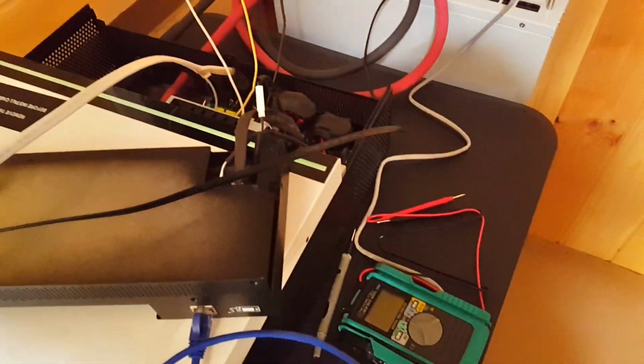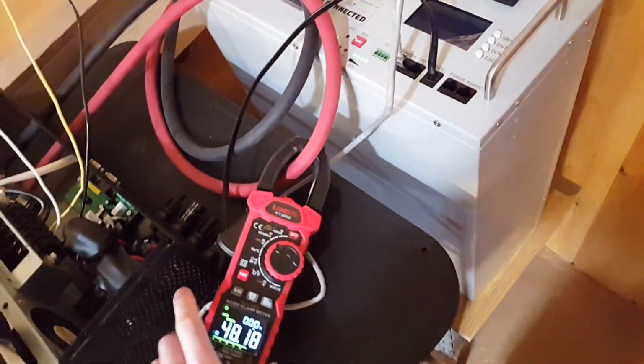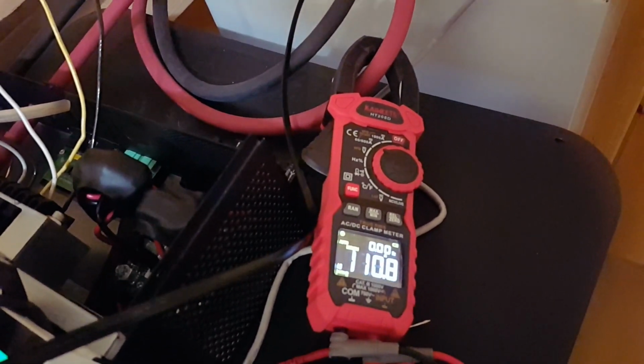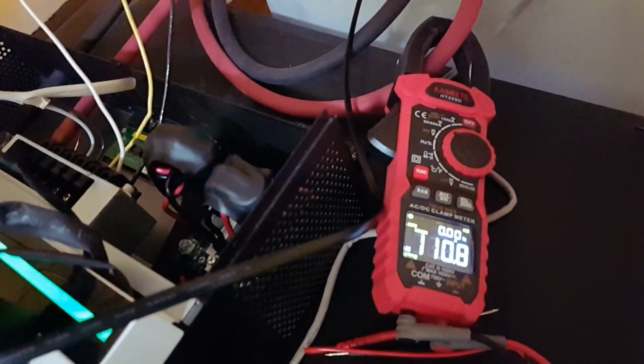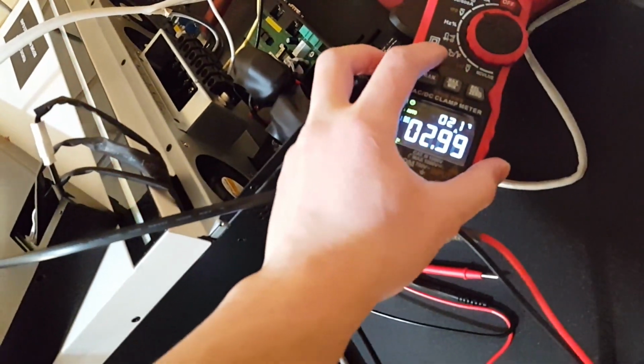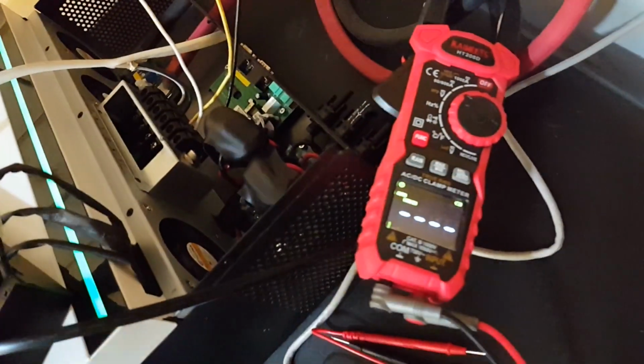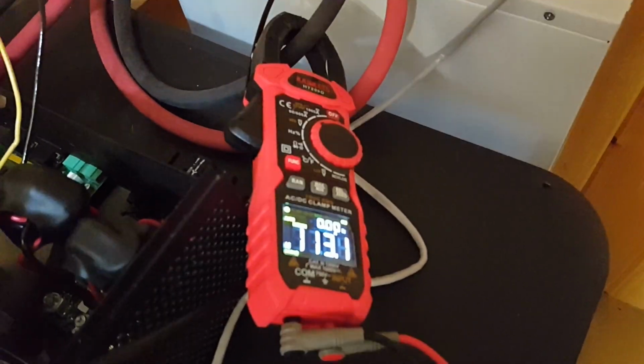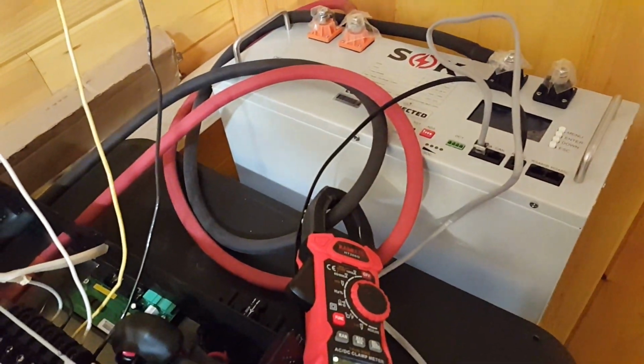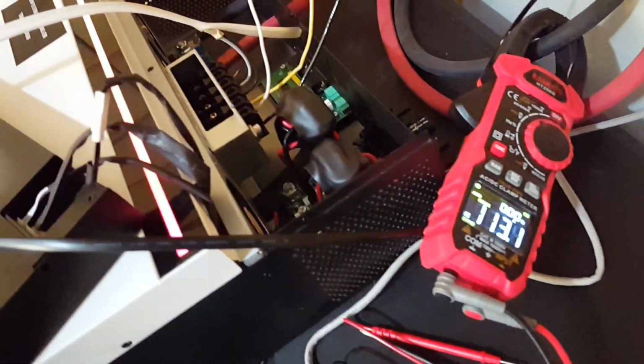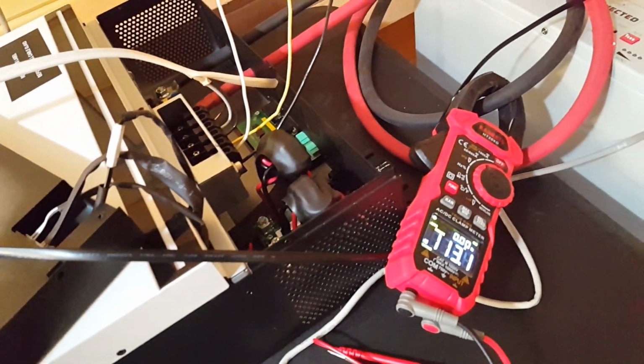Let's check the AC surge amps on the AC side. Sorry, my mistake. The DC. Let's check the DC side. 110 for the inrush. Let's try the other cable. Shouldn't be that much different. Nope, it didn't do it this time around. Failed again, even though the surge said 113. Even the compressor like this is too much.